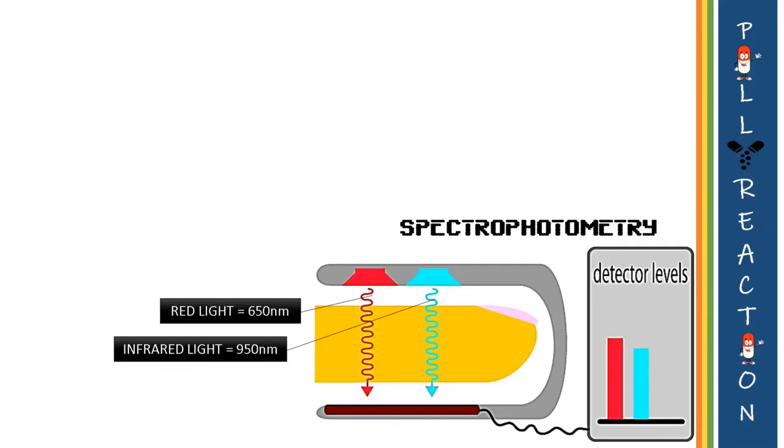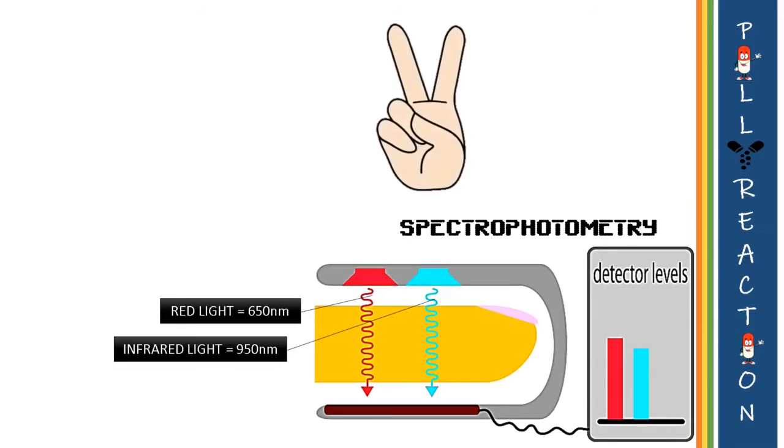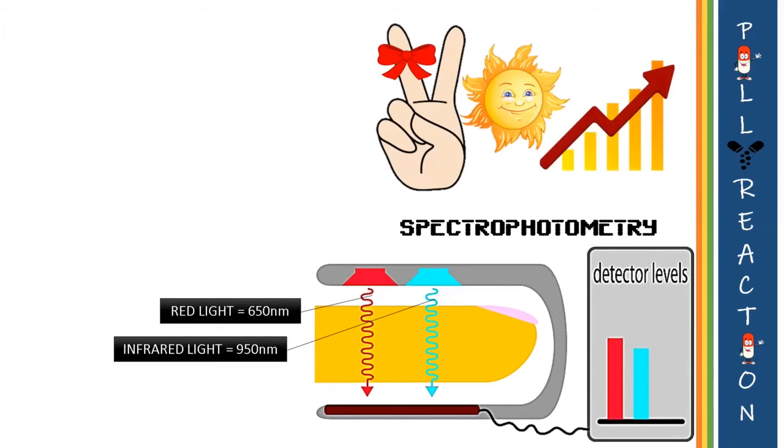The device also undergoes some extra calculations such as the size of the finger, any other surrounding light such as sunlight, and even absorbance of light by the rest of the tissues other than oxy and deoxyhemoglobin. The device even has a reference curve saved in its memory for the accurate, precise outcome that it provides.